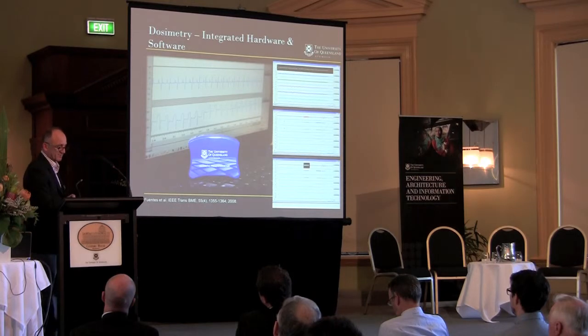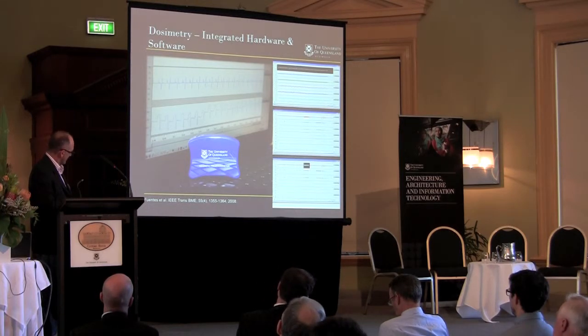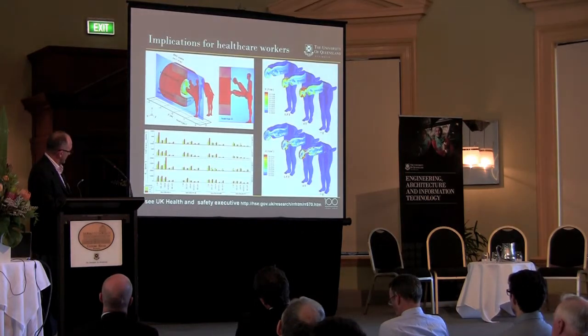There was outrage in Europe amongst the community, but the European Union wanted a third party removed from Europe to do some studies. At that time, there was no way to measure the fields that workers were exposed to or to model it effectively. So we ran a project for a couple of years and developed a small device that you could put in your pocket, similar to an ionizing radiation tag, that was able to measure static magnetic fields over a shift. So we could record exactly the exposure that workers were getting, and then we could model it.